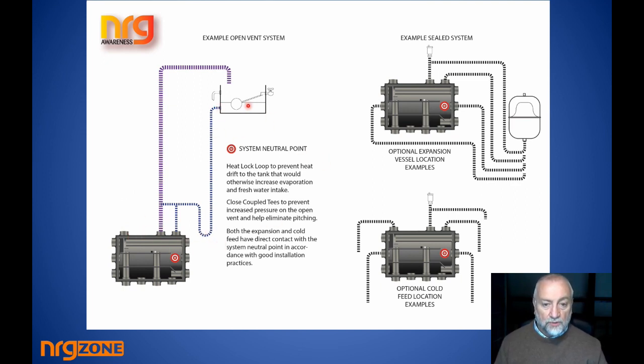So we would always recommend that you put in a heat lock loop that travels down below where you're actually going to go to, then turns back up. In fact, I'm showing here maybe visually about 200 mil. I would strongly suggest at least 350 mil if you can have at all with your cold feed loop down. That almost definitely prevents any heat drifting down and back up to the tank. If it is starting to go to the tank, the amount that's traveling will typically be radiated away from the surfaces of the cold feed and won't actually reach it.